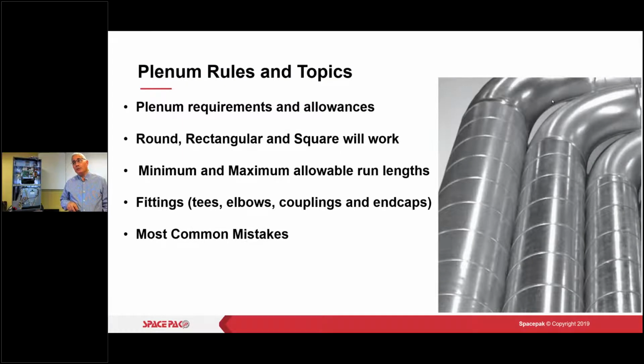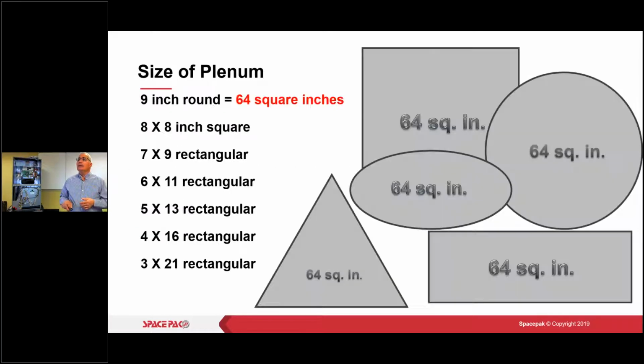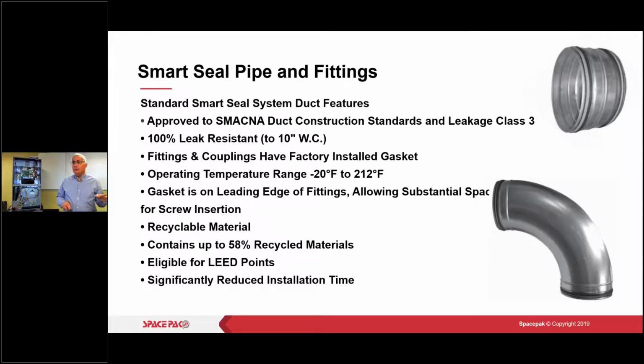So plenum requirements: make sure that we balance our system, that we have at least 50-50, 60-40, things of that nature. Round, rectangular, or square will work. Again, as long as I've got 64 square inches equivalent, I'm good to go, okay? So any of these configurations will work. The main number to remember is 64 square inches. As long as I've got that, I'm good to go. Right? So use all of our equipment. You can see the operating range. You can see the gaskets. All right. It makes a much more robust system.